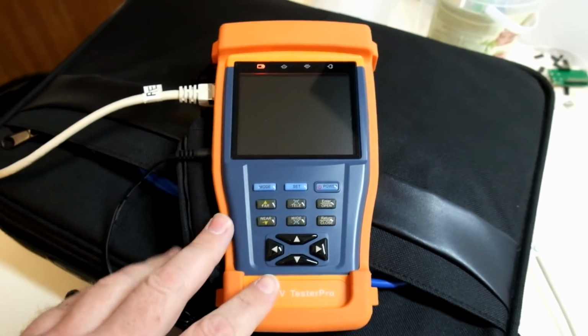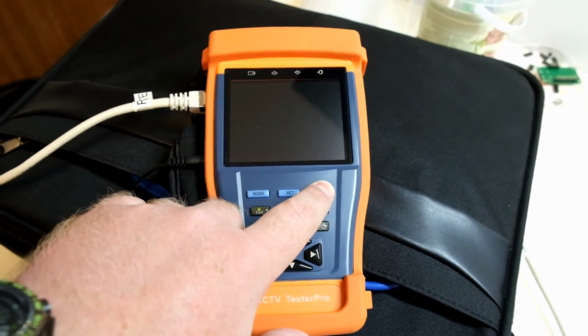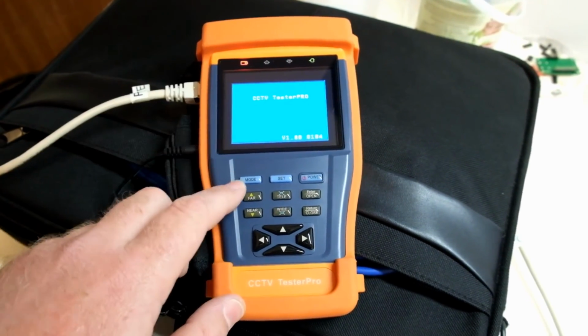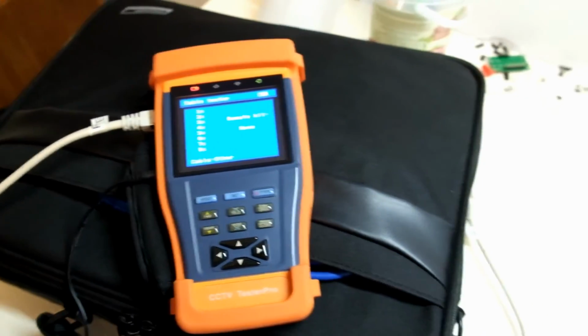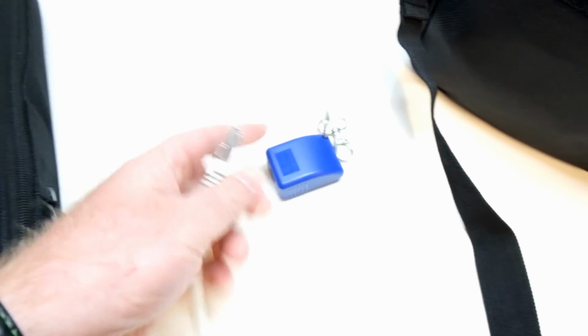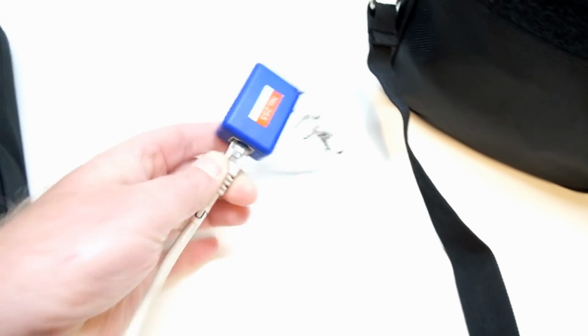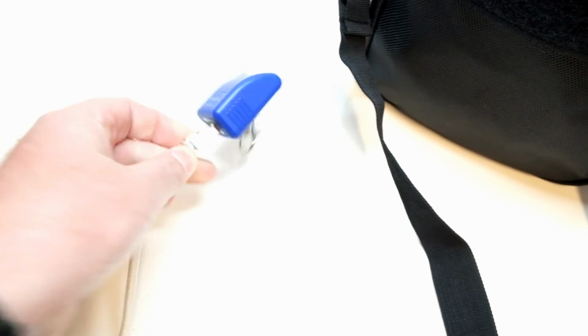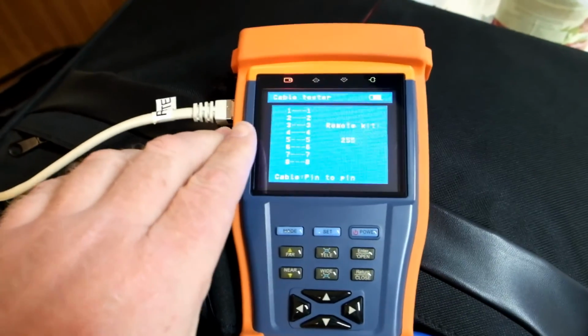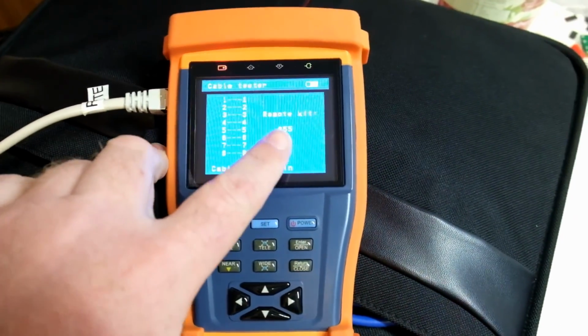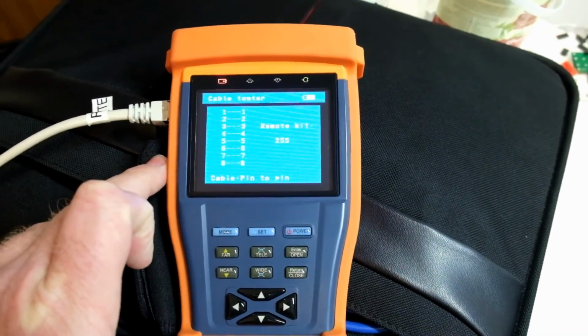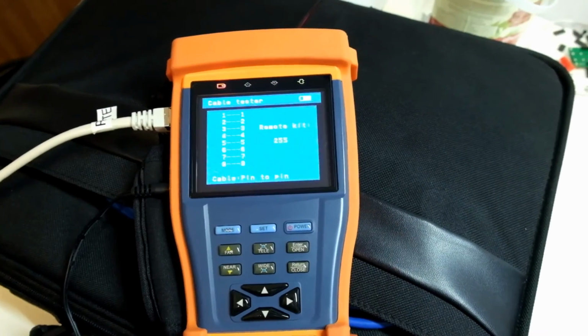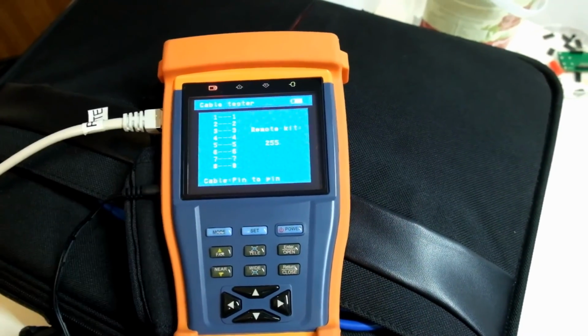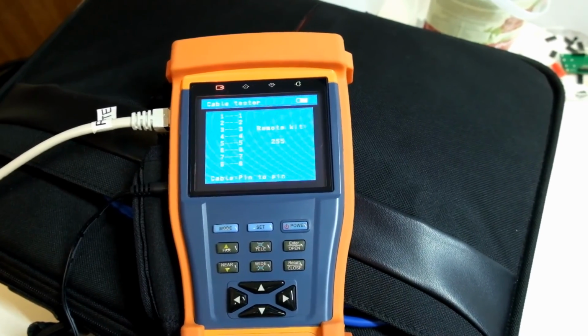This video is purely about what I use, what I have - and that's pretty much answering why I would keep a CCTV tester with my IT toolkit. One reason is this little section on the side. You can take a tester like this, which comes with it, and plug one end of your lead into the tester. Bearing in mind this tester is 255, there you have it - full cable test, all cables connected 1 for 1, kit code 255. So straight away we can identify this cable is connected to the 255 transmitter and the cable is fine. That's one very big reason.